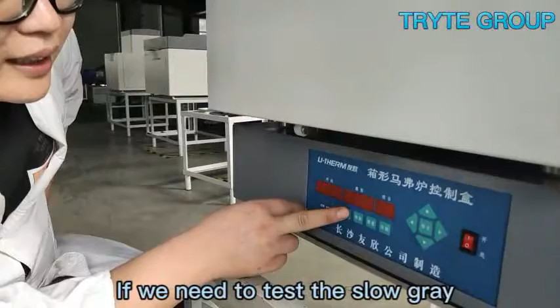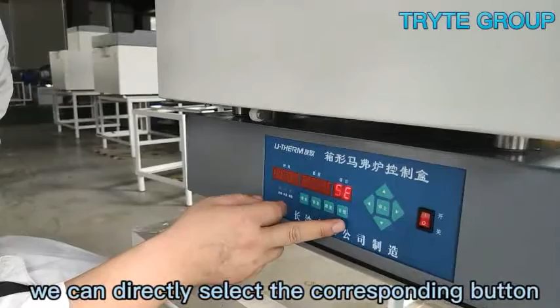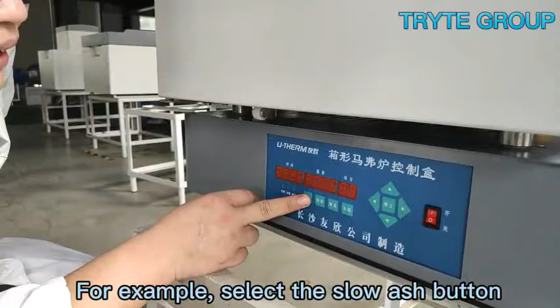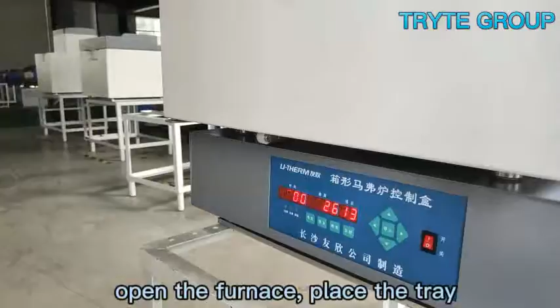If we need to test the slow ash, fast ash or volatilization of the sample, we can directly select the corresponding button. For example, select the slow ash button. The instrument prompts you to open the furnace. Open the furnace.